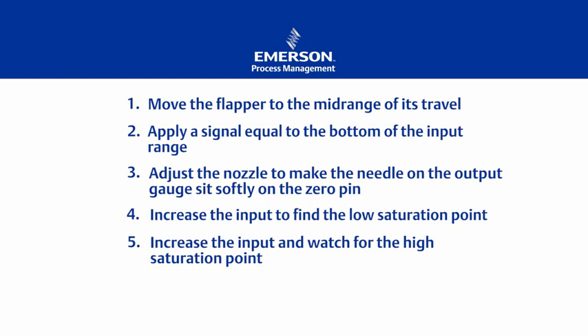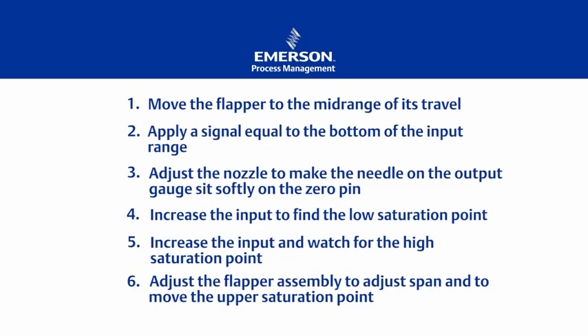Step five, increase the input and watch for the high saturation point. Step six, adjust the flapper assembly to adjust span and to move the upper saturation point. Then re-zero and check it again.